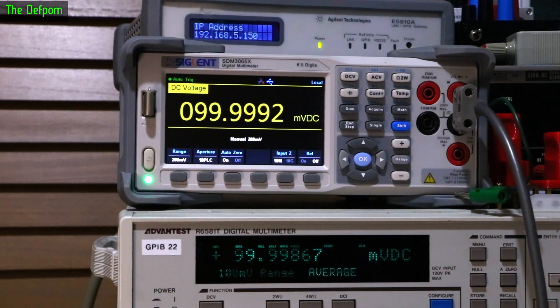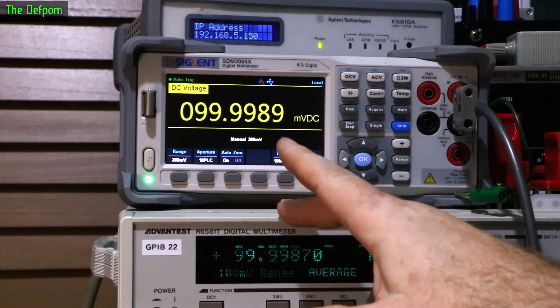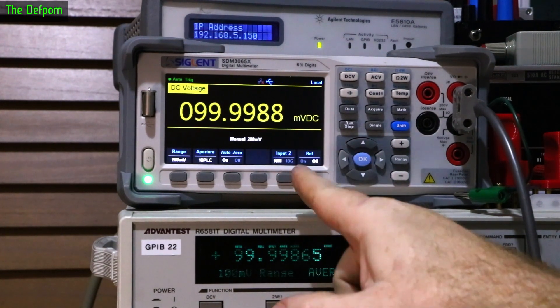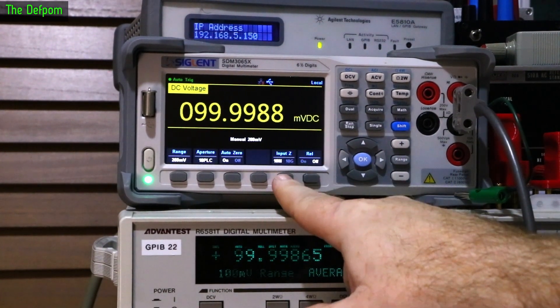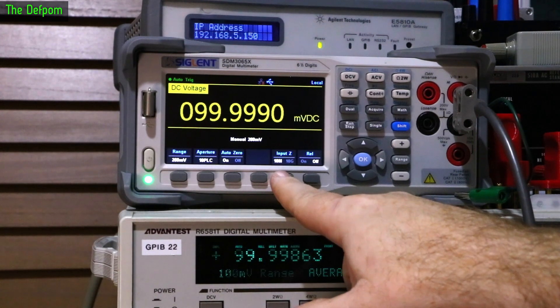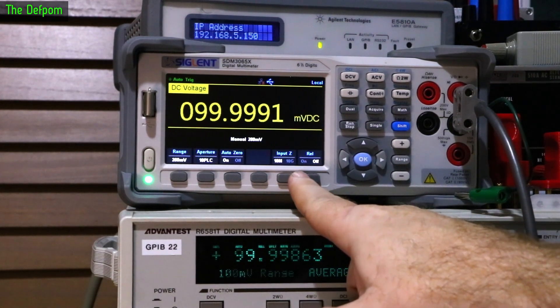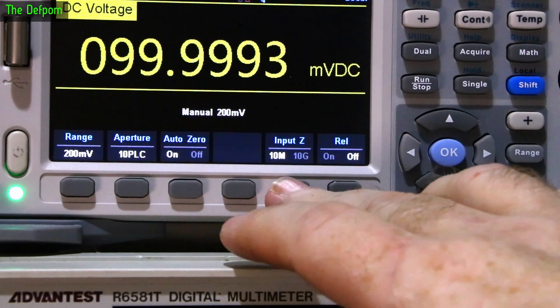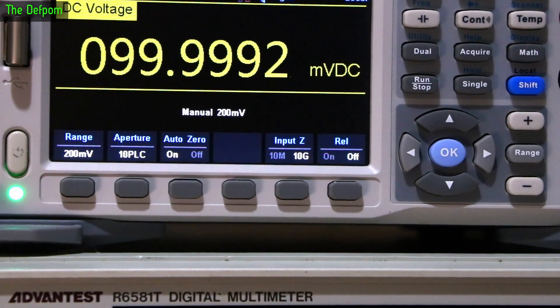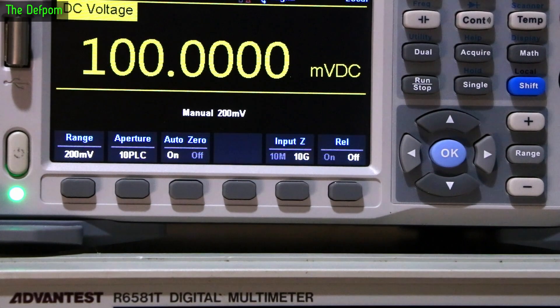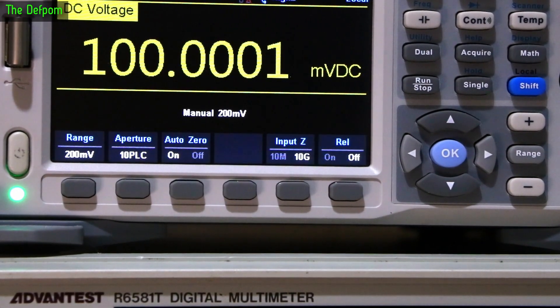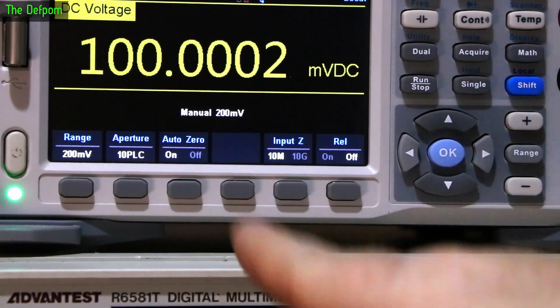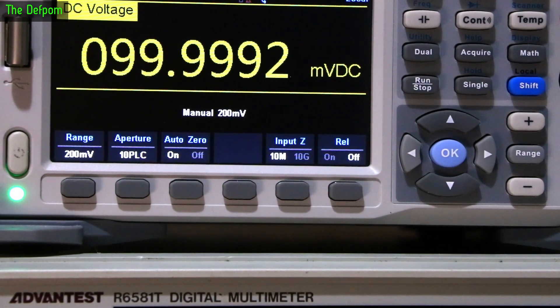I thought I'd show you one more thing. On this particular meter, I think only the 3065X has got it - input Z, input impedance. It's currently set to 10 meg. On this one you can actually do 10 gig. Watch this meter reading when I go to 10 gig instead. See, just doing that can affect your readings. Certainly consider that. But as long as it's calibrated to the way you're going to use it, it shouldn't actually matter.